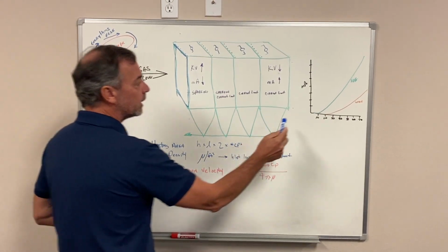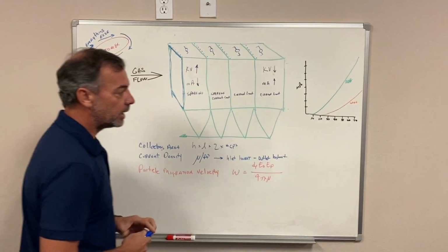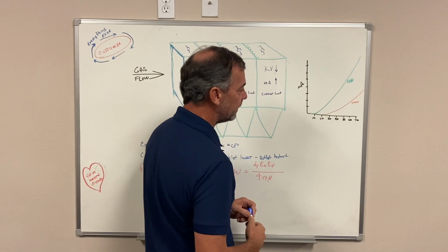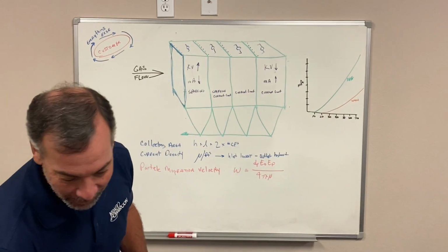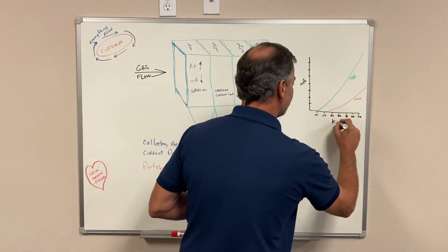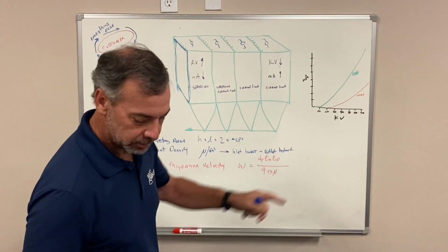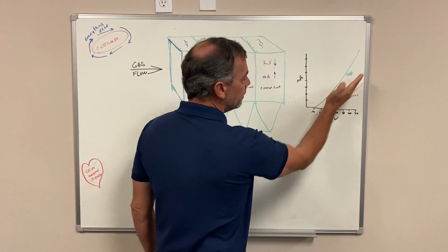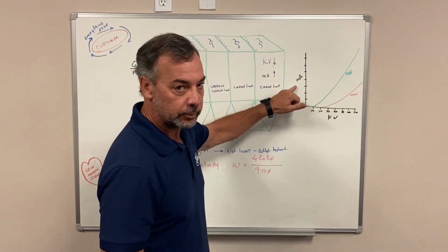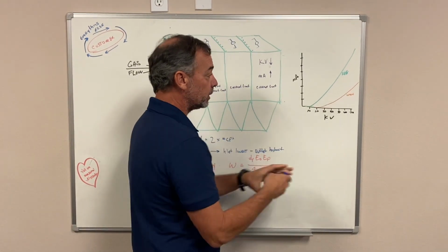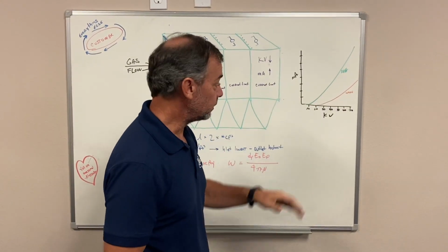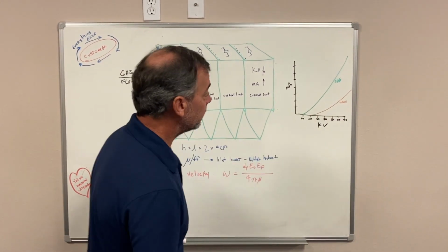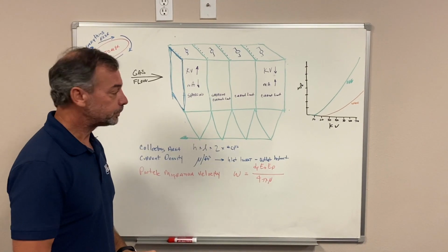So we'll come back over here to a VI curve. As you increase in voltage, we have kV down here on the bottom. I didn't write that in there, I'll do it now. And milliamps along the y-axis. So as we increase in voltage, we're going to draw more current from the transformer. And it's different between a wire or a rigid discharge electrode. A wire has a little bit flatter line, and the RDE has a sharper VI curve.